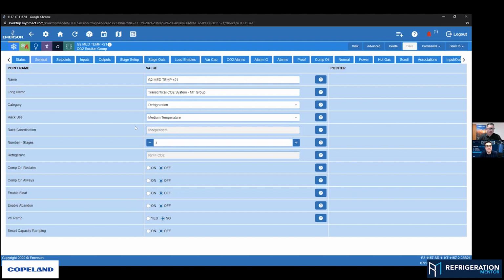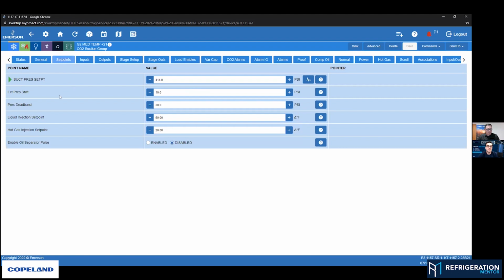For medium temperature, when we move to the set point tab, you get liquid injection, hot gas injection, and oil separator control. Whereas with low temperature, it doesn't give you those options, because most low temperature systems on the booster transcritical side don't require the liquid or hot gas injection, and most don't even have a separate oil separator since they discharge straight to medium temperature suction headers. We don't need it there, so why show it? That's the idea of having those there or not.